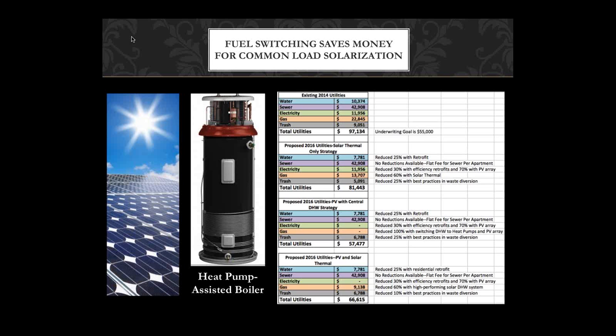At the bottom, we did a run with PV and solar thermal while keeping the gas in, and found that the inability to offset more than about 60% of a gas load for solar thermal — 60% of domestic hot water load — means you're spending more money on the roof but getting less benefit. So that's how this owner is moving forward: yanking out the boilers, putting in heat pumps, putting PV on the roof to offset the new electrical demand, and making money.